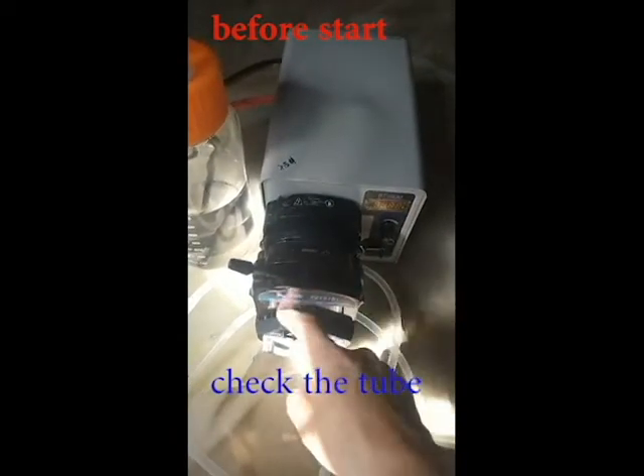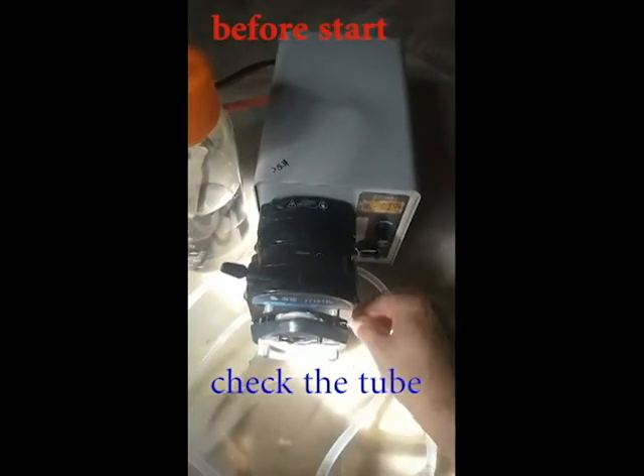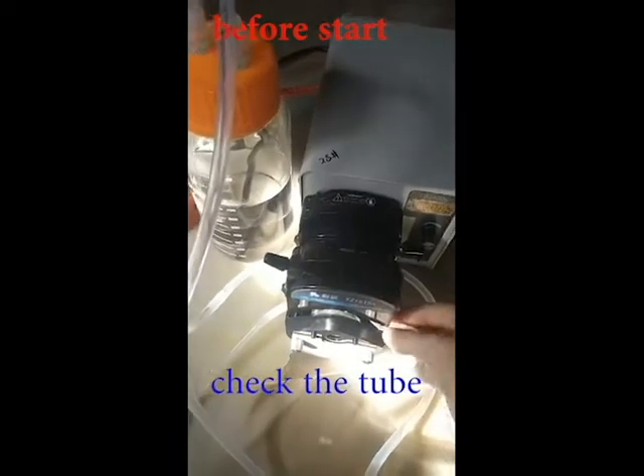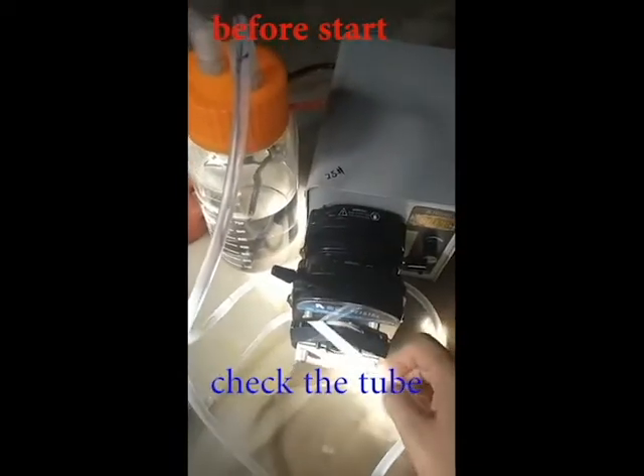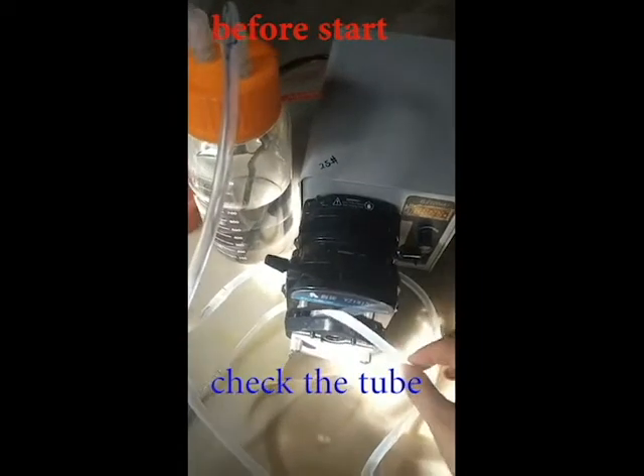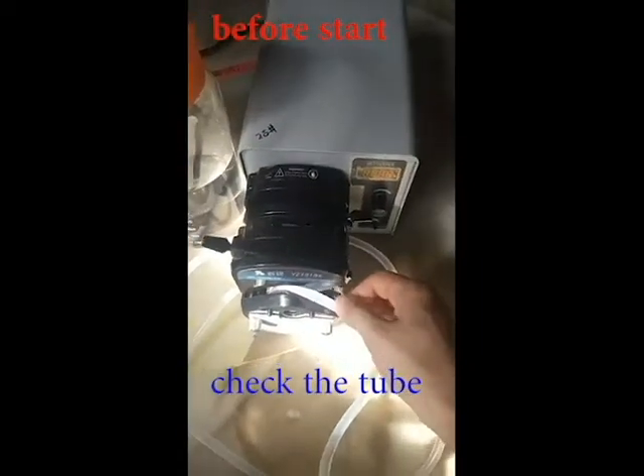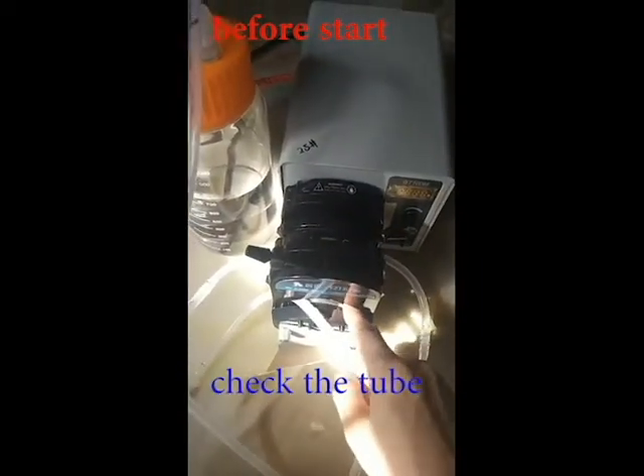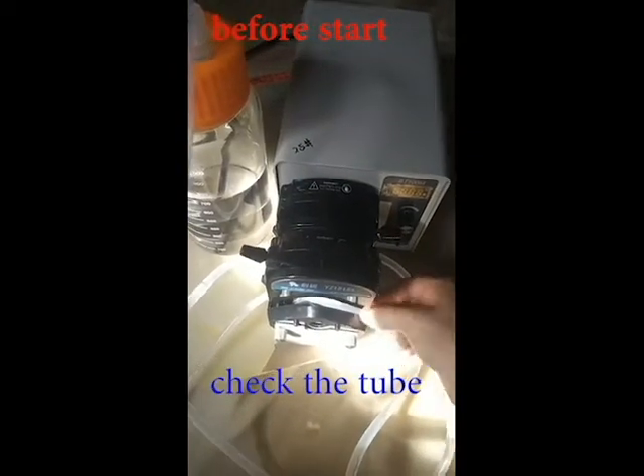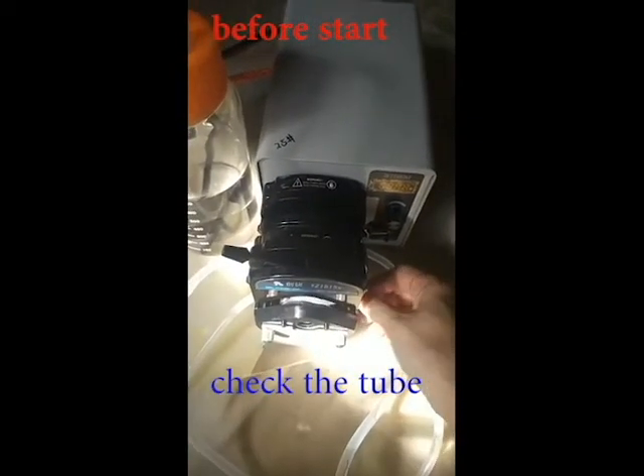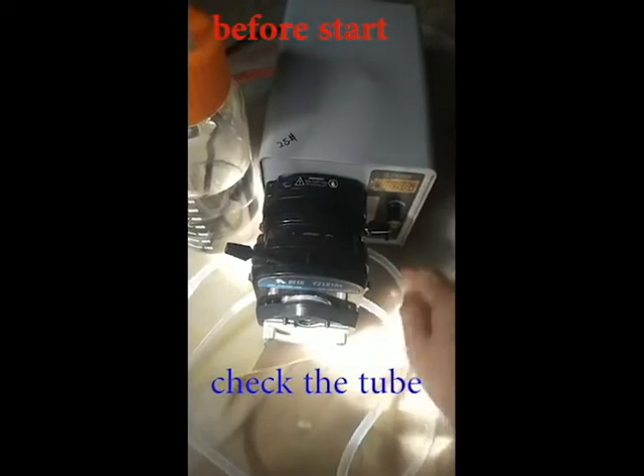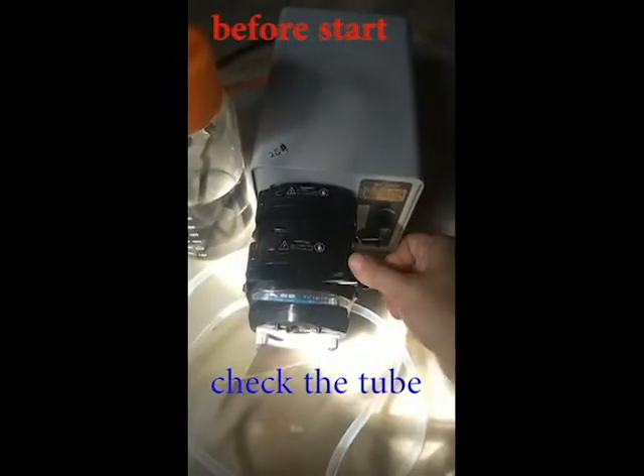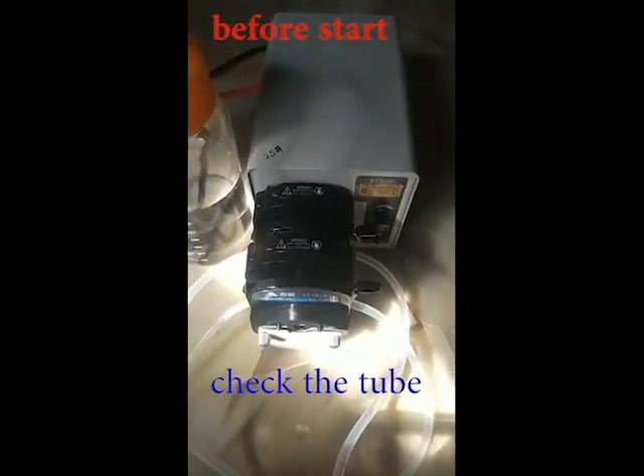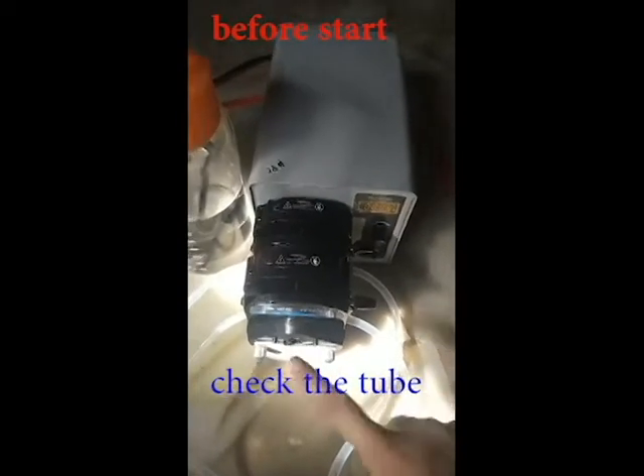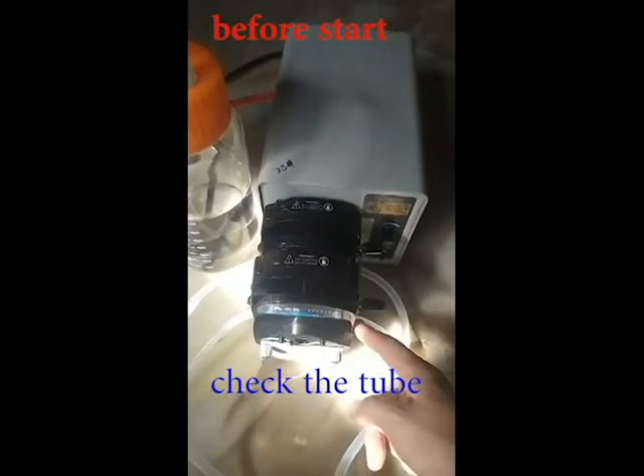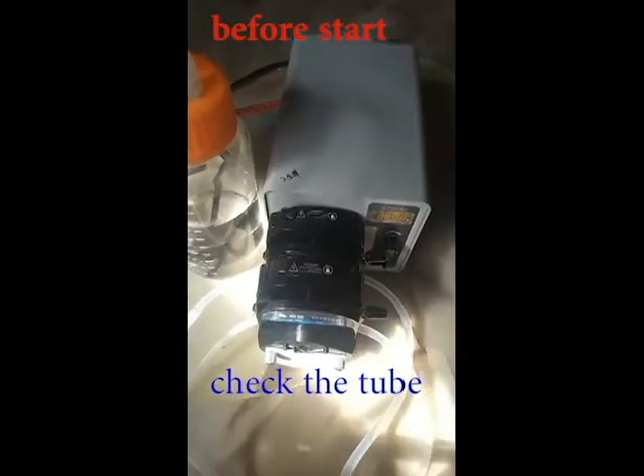If it's not clean, you can take the tube out. Take the tube out and wipe it with a clean cloth. Then the rotator, do the same and make sure it's clean. Then you insert the tube, close the pump head, and you can start to use. Every time make sure the tube is clean and the rotator is clean.